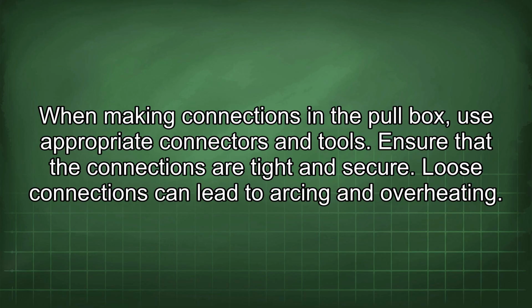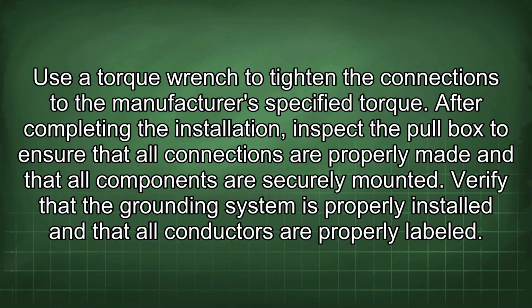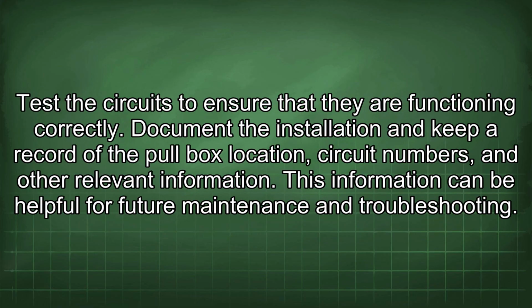When making connections in the pull box, use appropriate connectors and tools. Ensure that the connections are tight and secure. Loose connections can lead to arcing and overheating. Use a torque wrench to tighten the connections to the manufacturer's specified torque. After completing the installation, inspect the pull box to ensure that all connections are properly made and that all components are securely mounted. Verify that the grounding system is properly installed and that all conductors are properly labeled. Test the circuits to ensure that they are functioning correctly. Document the installation and keep a record of the pull box location, circuit numbers, and other relevant information. This information can be helpful for future maintenance and troubleshooting.